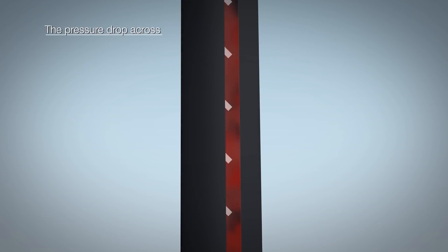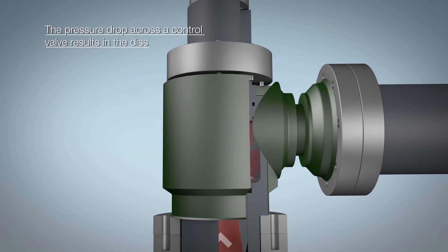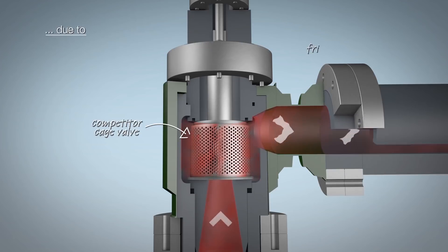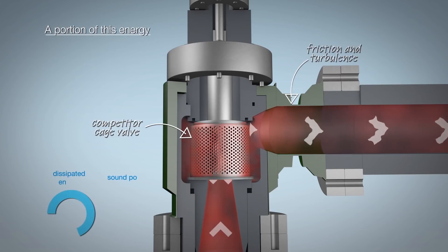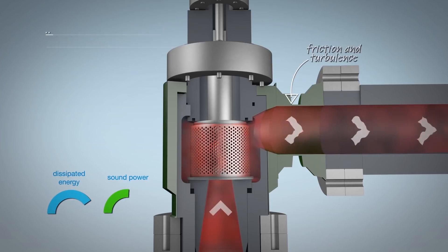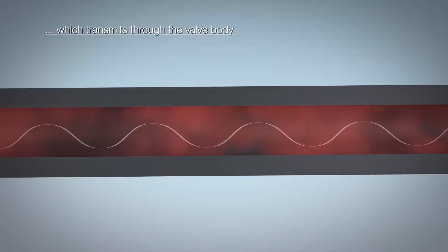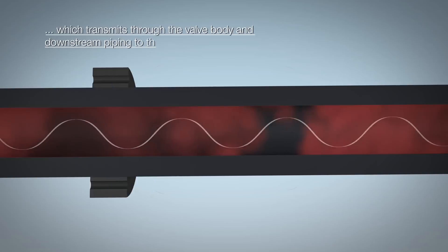The pressure drop across a control valve results in the dissipation of energy due to friction and turbulence. A portion of this energy is converted to sound power, which is transmitted through the valve body and downstream piping to the surrounding area.